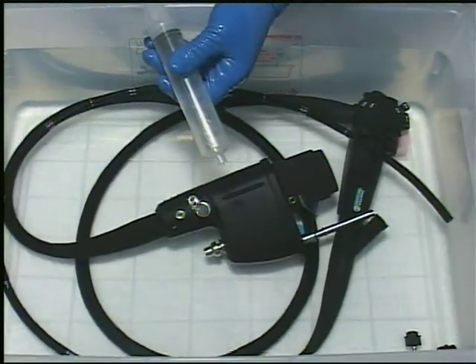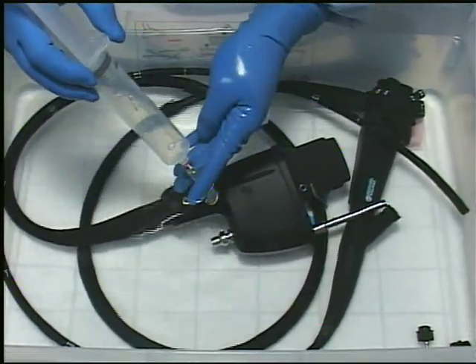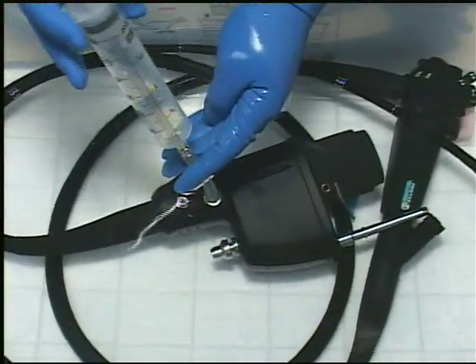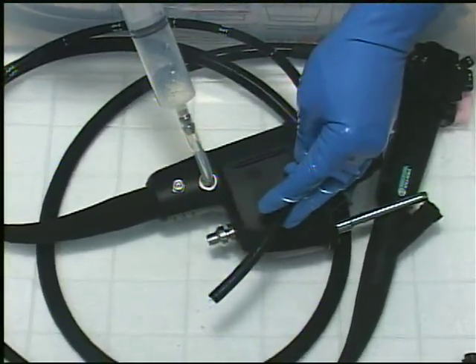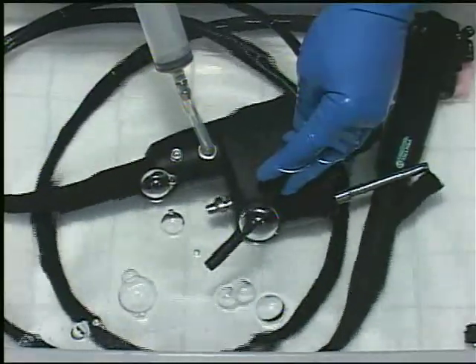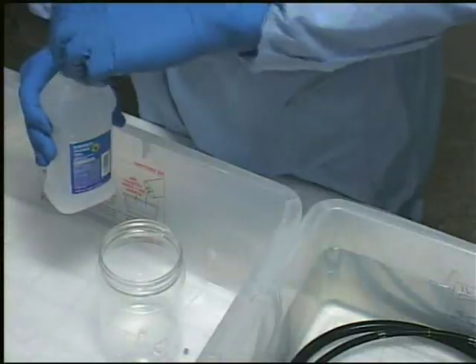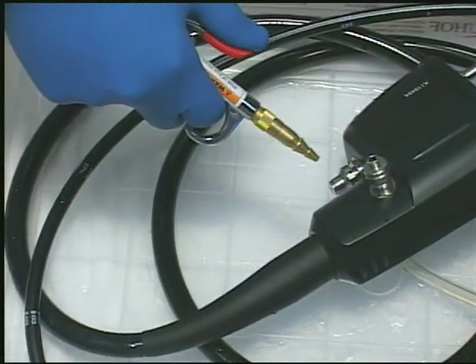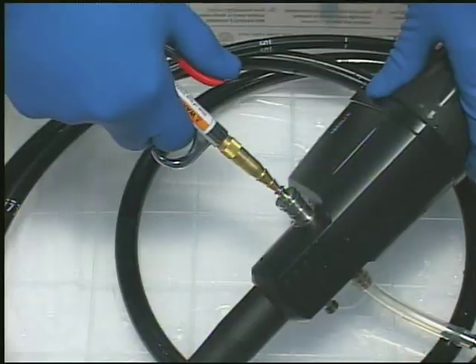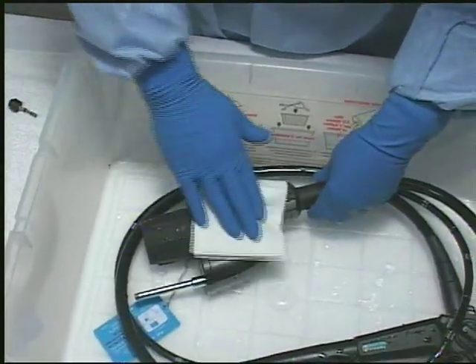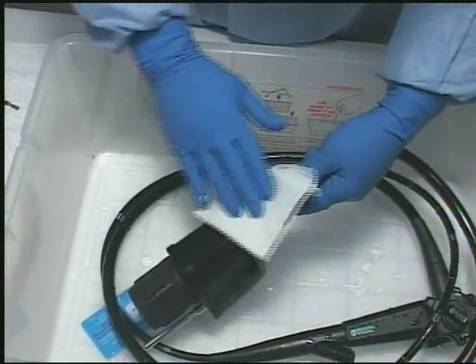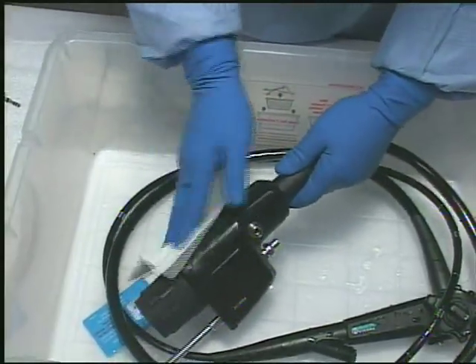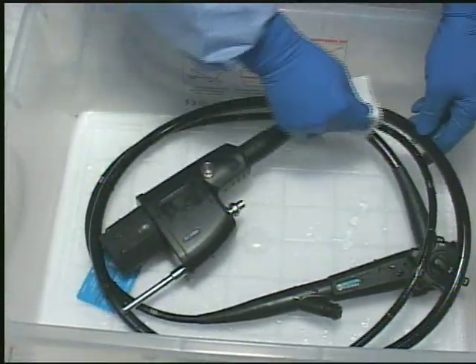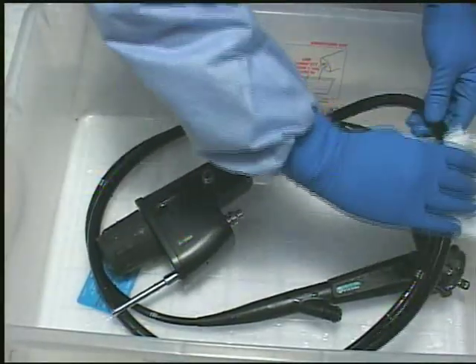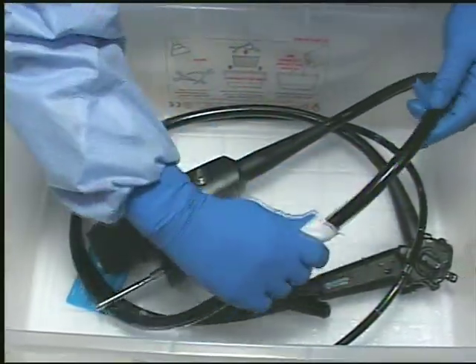Rinse water remaining within the channels should be purged with air to prevent dilution and/or adulteration of antimicrobial agents to be used in the subsequent disinfection or sterilization process. Note: 70% alcohol followed by compressed air, not greater than 24 psi, may be used to facilitate drying. Gently dry all external surfaces of the endoscope with a soft gauze or the like. Do not put tension on the insertion tube of the endoscope while drying, since the outer cover of the bending section may be excessively stretched.